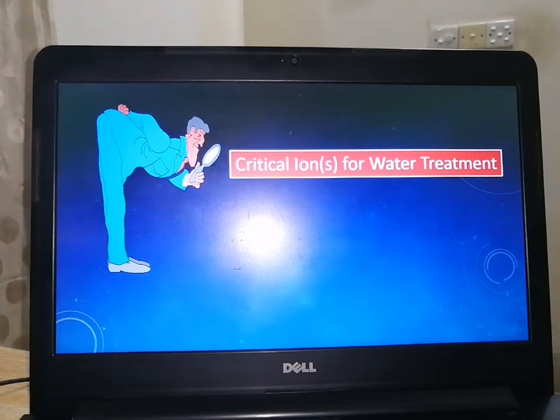Before going to critical ions, yesterday we talked about cycle of concentration. So what is cycle of concentration actually? Cycle of concentration is any ion in the cooling system's blow down water divided by the same ion in the makeup water. This is the cycle of concentration.